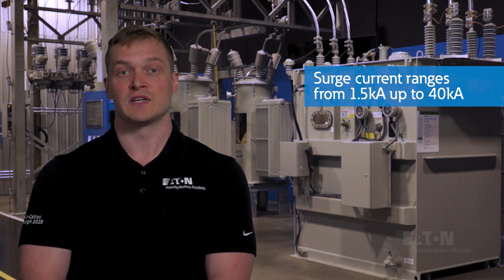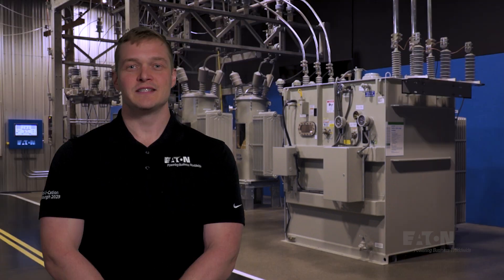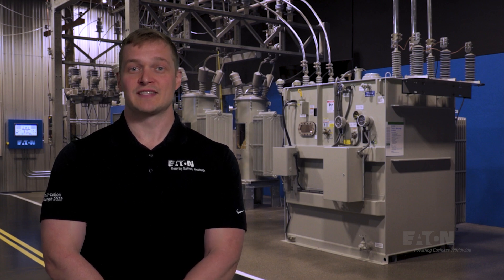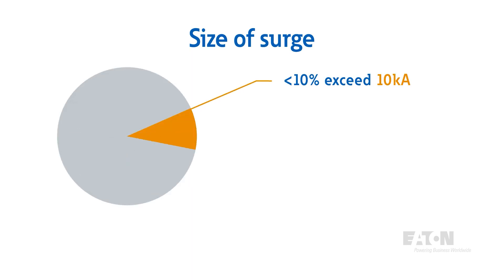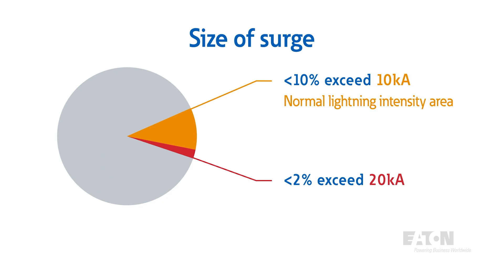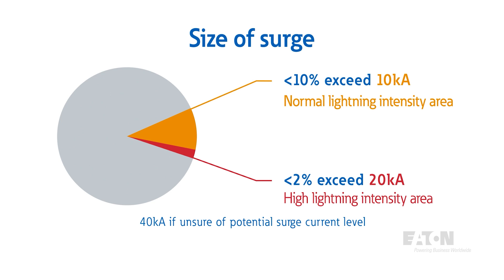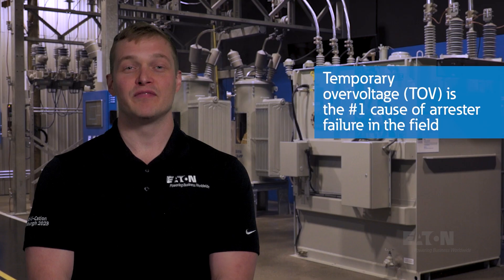The higher the surge current, the higher the discharge voltage, resulting in a lower margin of protection. Data collected over the years suggests that less than 10% of surges exceed 10 kA, and less than 2% exceed 20 kA. Using these two data points as a guide, most utilities select 10 kA surge current ratings for normal areas and 20 kA for high intensity areas. 40 kA may be used to ensure protection in case you are unsure of the potential surge current levels.